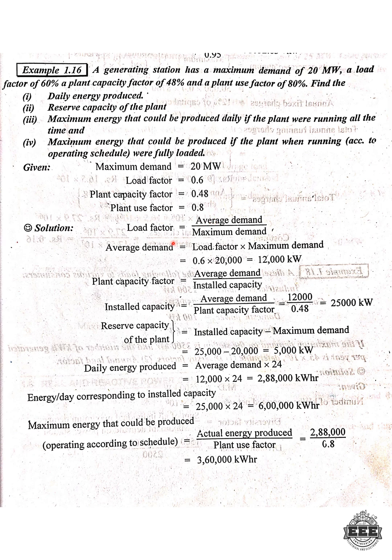Next, we calculate the average demand. The formula is: load factor equals average demand divided by maximum demand. So by cross multiplication, average demand equals load factor into maximum demand. That gives us 0.6 into 20,000, which equals 12,000 kilowatts. So average demand is 12,000 kilowatts.